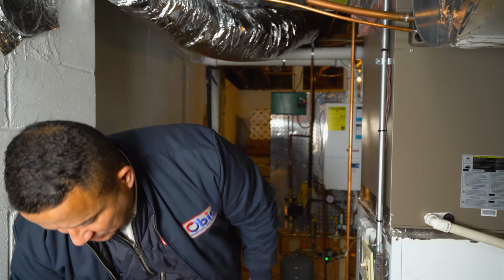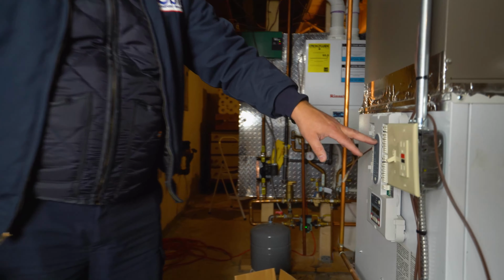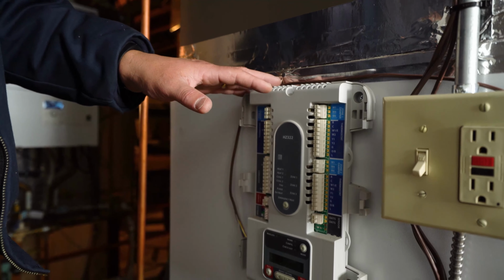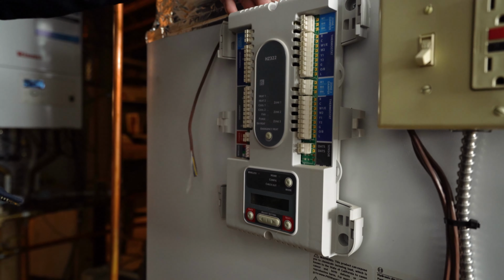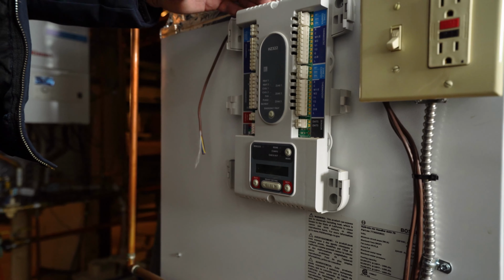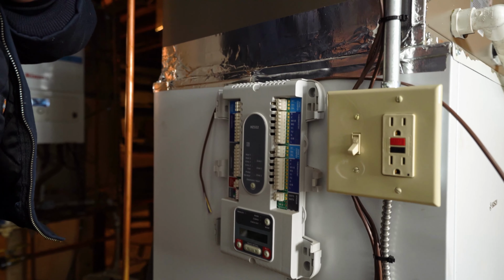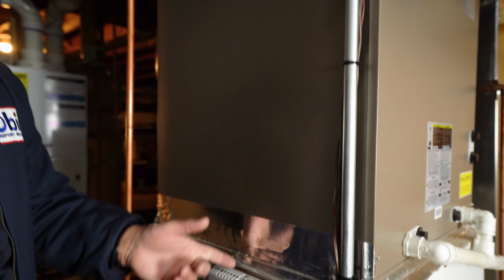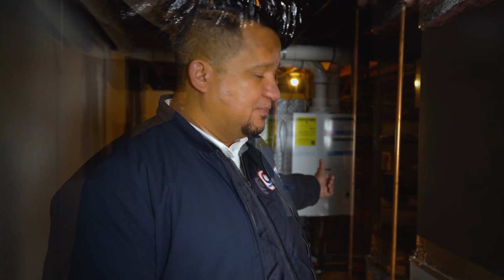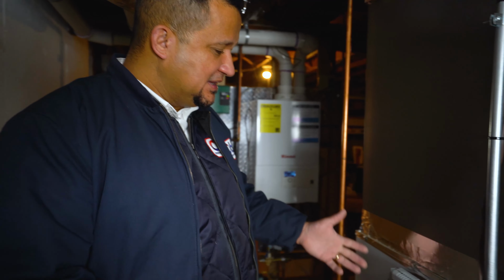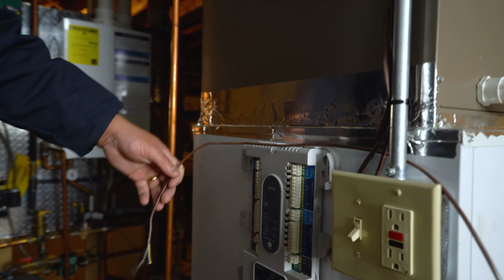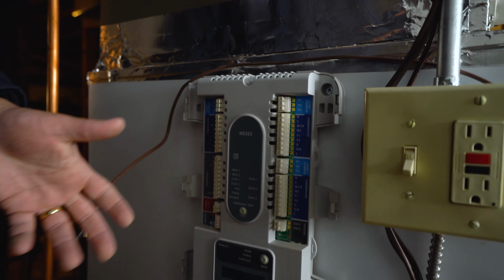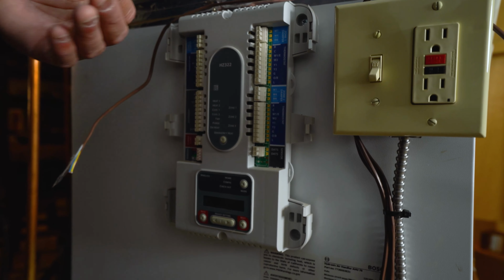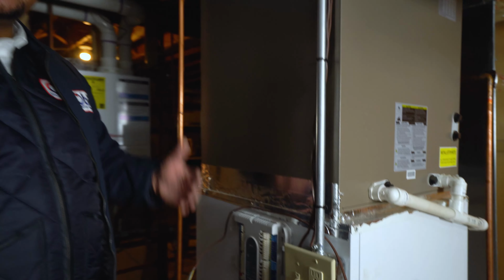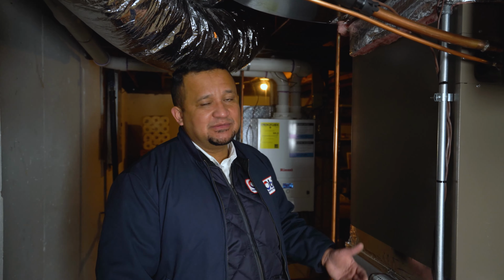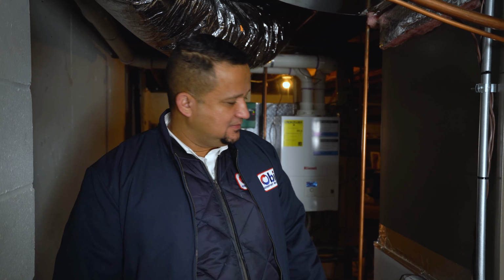This is controlled by this control panel, but it's the wrong controller. This is a dual fuel application, so we use the heat pump outside, and when the temperature drops below a set point, say 32 degrees, the system should automatically switch to the boiler. Right now it's not even wired properly. It feels like they tried to do this and couldn't figure out the proper way. That's the difference when you hire a company that's professional, trained, and has done this many times, versus one that's just trying it out.